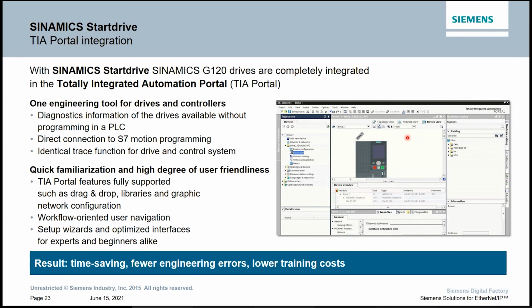The diagnostics have trace functions that let you trace pretty much any parameter or I/O from the drive, or data coming over the telegrams, and you can chart those as well. From a diagnostic standpoint, this is probably one of the best pieces of software I've seen.